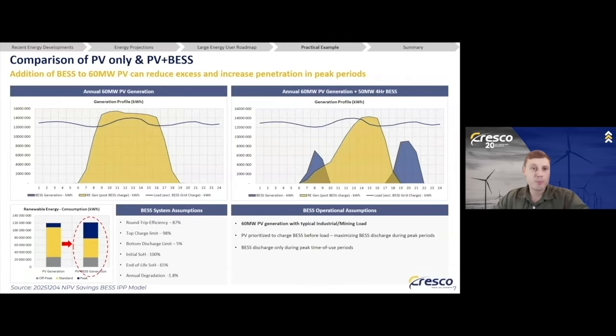So this is just a practical example showing a 60 megawatt PV system on its own, and then showing the same system paired with the 50 megawatt 4-hour BESS. And that's modeled against a typical industrial or mining load profile. And I think important just to note is that this is for an average day in the year. So one can expect more variation if you isolate the profiles in January or June, like previously shown.